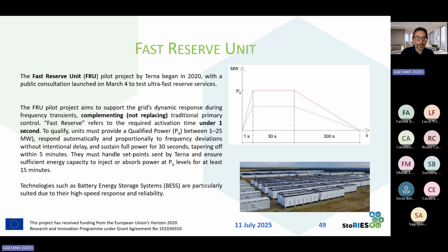I don't remember exactly, but for Italy it should be almost 250 or 300 megawatts of storage system necessary for this service, for replacing the power plants that will be decommissioned. And the fast reserve is operated in this way. Various units with rated power between 1 megawatt and 25 megawatts will be installed in the country, and they must be able to provide the full power in 1 second, maintain the injection of that power for 30 seconds, and then reduce the power injection into the grid in 300 seconds, in 5 minutes.